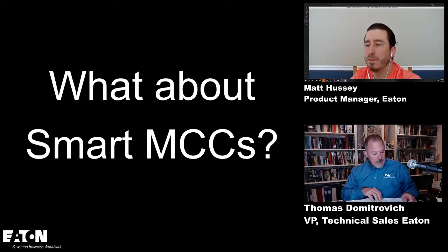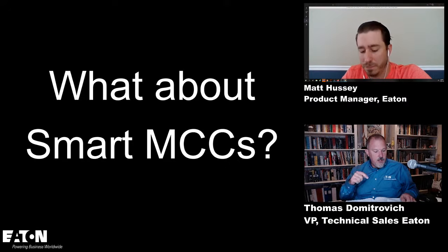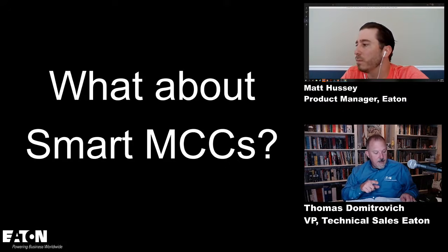So I guess that's probably a parameter you've got to think about with regard to placement. If you're going to be in an MCC, where that MCC is going to be located in relation to the fire pump controller and the transfer, all that good stuff. So it may be that the MCC you're going to is not within sight of the motors that they control. So proximity of that MCC in a fire pump application is probably going to be an issue.